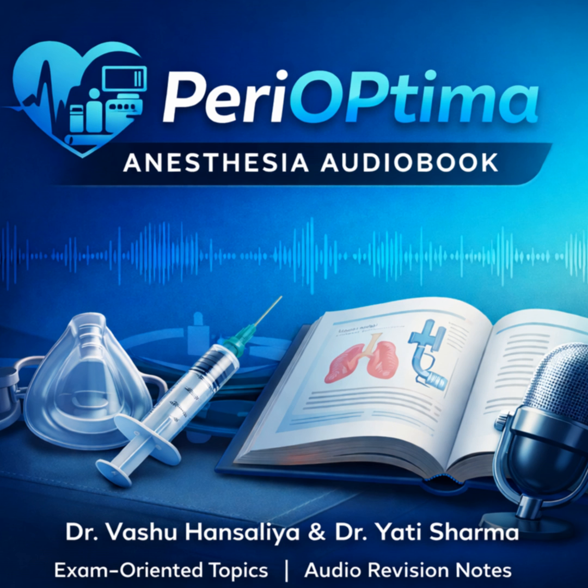It gets saturated with vapor, and then it rejoins the bypass gas. The dial on top basically controls that splitting ratio. A higher percentage means more gas goes into the vaporizing chamber. But there's a physics problem here, isn't there?